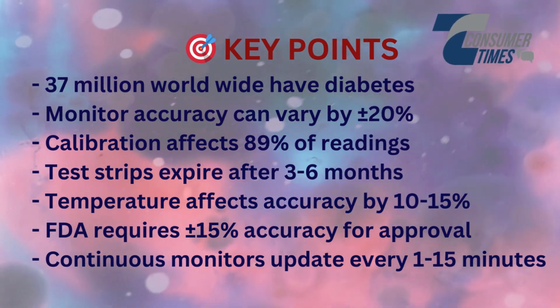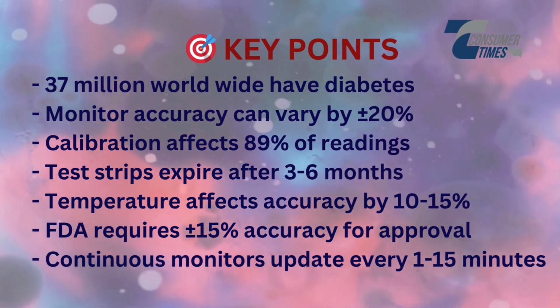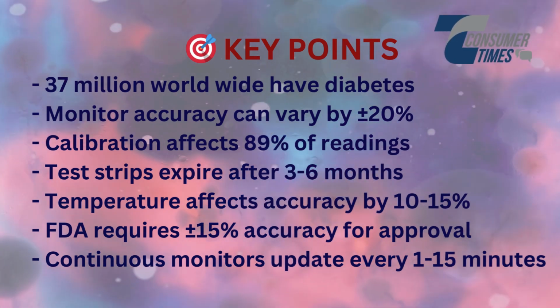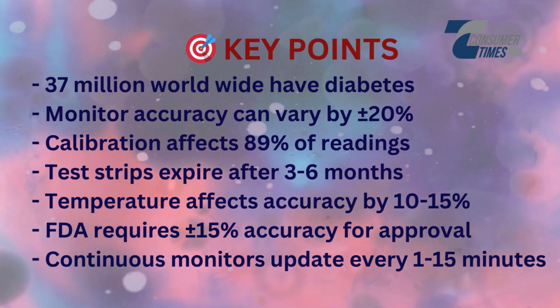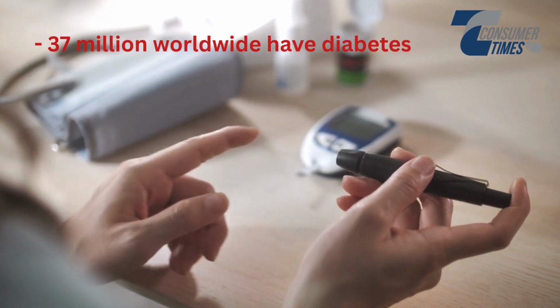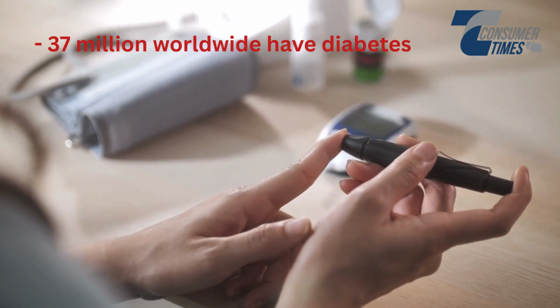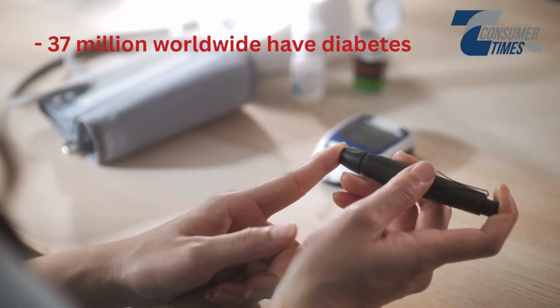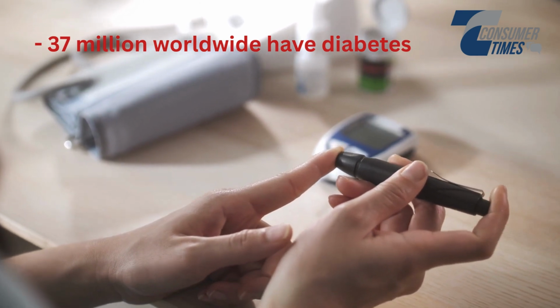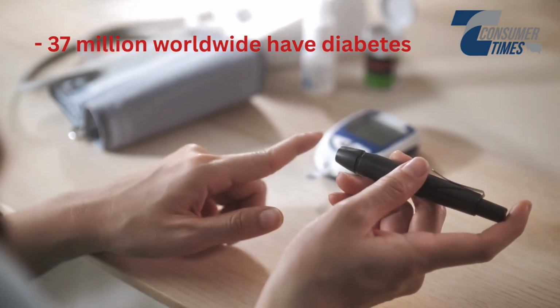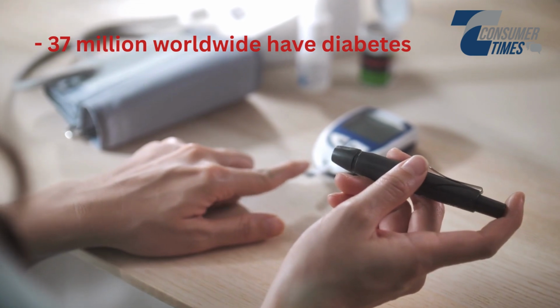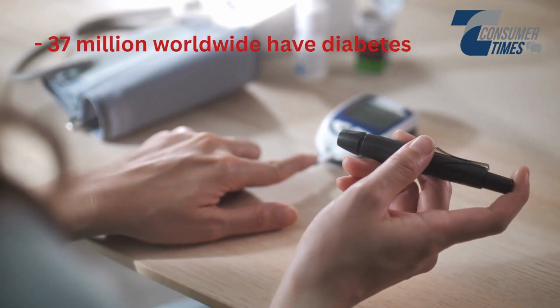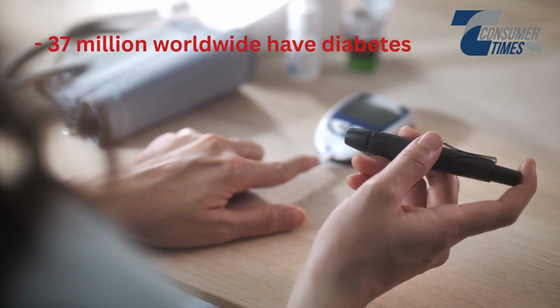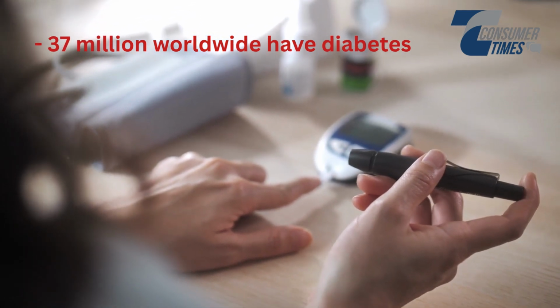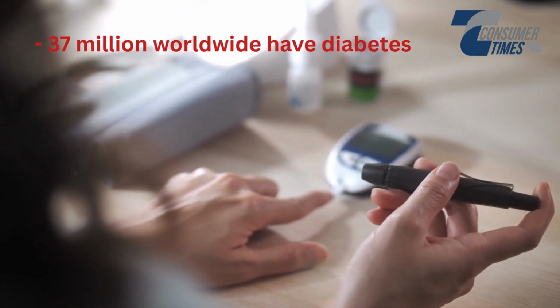The accuracy of these devices depends heavily on proper calibration. Most people don't realize that factors like altitude, temperature, and even humidity can affect readings. We tested 5 popular models under controlled conditions and found accuracy variations of up to 18% between devices using the same blood sample. Now, let's talk about continuous glucose monitors, or CGMs.